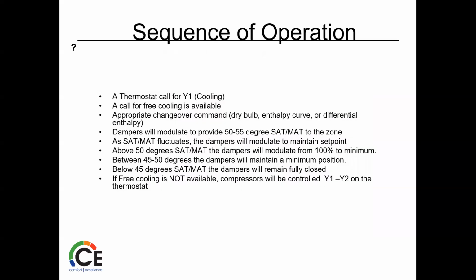So, basic sequence, right? Thermostat calls for Y1. If it's cold enough for free cooling, we operate in free cooling. We're pulling in that cold ambient air. And then we don't need a compressor at that point because the air outside is cold enough. We're cooling off the space. Appropriate changeover command, whether you have a dry bulb or an enthalpy curve or a differential enthalpy. Again, that's up to what we're trying to do and how we have the unit set up.